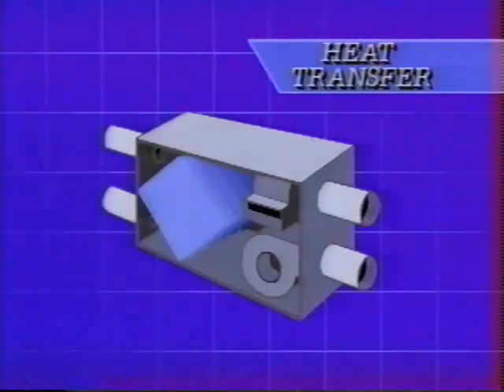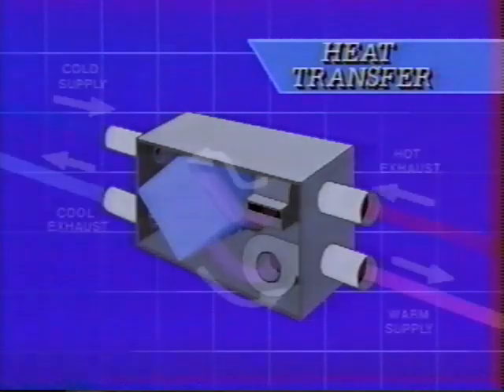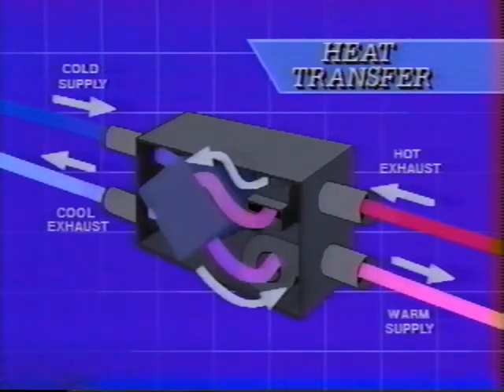What happens is we have an HRV set up here for a demonstration. The cold outdoor air comes in through the heat exchanger on this end. The warm exhaust air comes out through there. As they pass in the core, the heat is transferred from the exhaust air to the supply air. This is important in that it helps to warm the supply air so you can eliminate problems that you would have with bringing in cold, fresh air into the house.